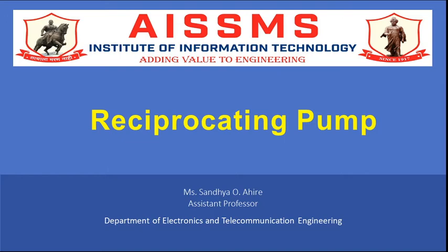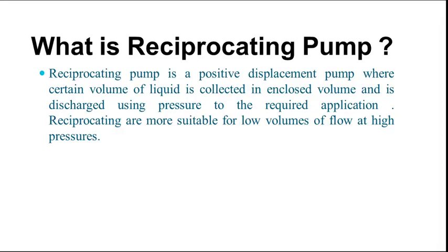In this video, I am going to explain reciprocating pump. What is reciprocating pump? Reciprocating pump is the positive displacement pump where a certain volume of liquid is collected in an enclosed volume and it is discharged using the pressure to the required application. Reciprocating pumps are more suitable for low volumes of flow at high pressure.